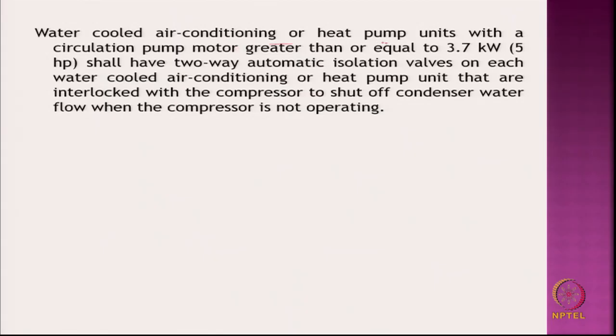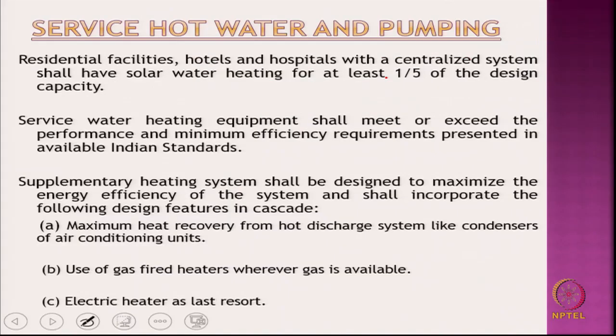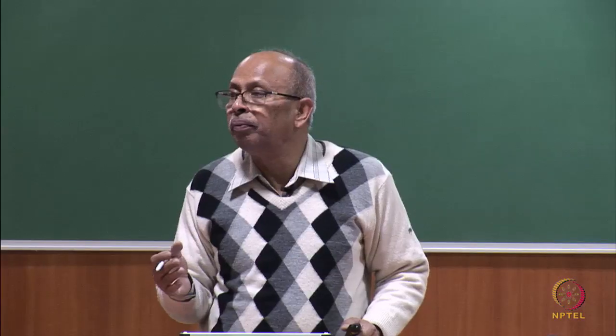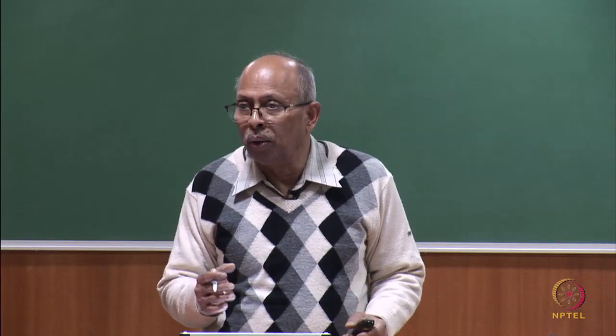Okay. Water cooled air conditioning or heat pump units with a circulation pump motor greater than or equal to 3.7 kilowatt shall have two-way automatic isolation valves. Water cooled air conditioning or heat pump units that are interlocked, that is, if you have both together, then you should have isolation valves. So, if one goes, the other does not work. Similarly, such prescriptive requirements are also given for service hot water pumping. That means, these are mandatory requirements, even when you have a trade off option.